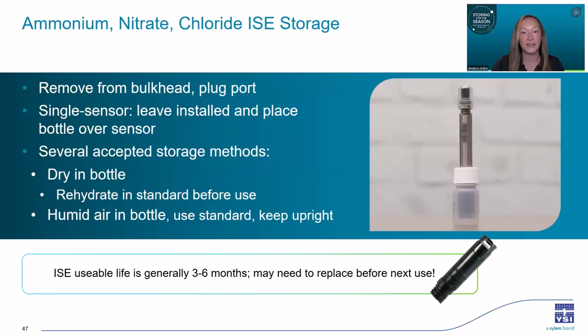One option is to store the ISE dry with nothing in the bottle. If you do leave it dry, it's important to rehydrate that membrane before the next use by soaking it overnight in the standard that's closest to your expected measurements. The reason that we still will put a bottle on it even dry is just to protect that tip or that membrane.